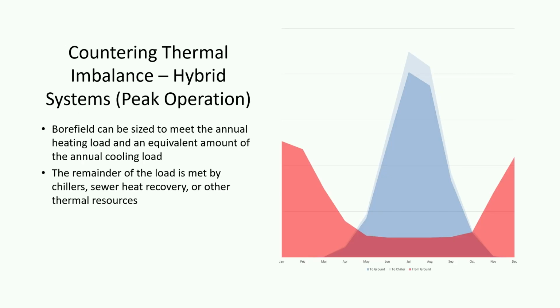Now, as we said, a lot of times you're limited by space constraints or drilling depth constraints, or it may cost more to drill deeper or further. So another type of system that we look at, we call it a hybrid system. What you'll do is you'll size your bore field, you'll meet the heating load, or as much of it as you possibly can, and then whatever you cannot meet with that, the cooling load, you'll meet with some other thermal resource. So in this case, we're calling it peak operation.